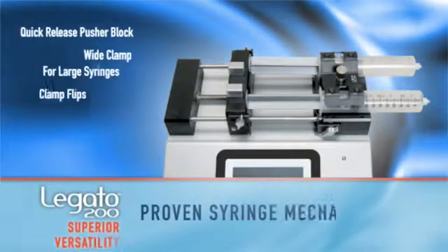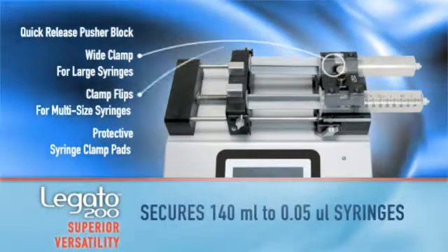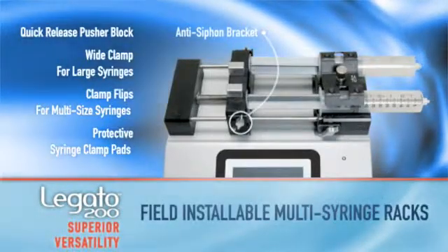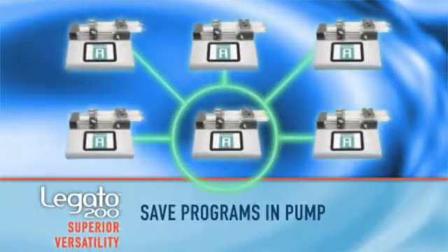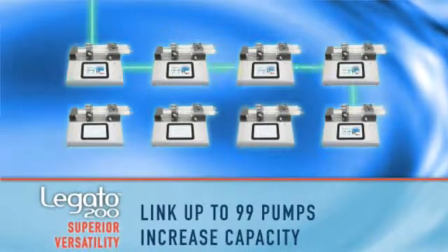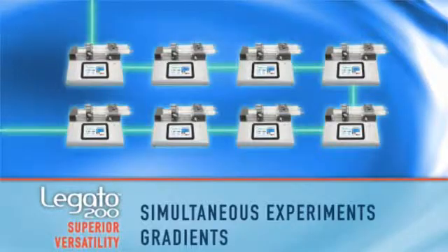Take, for example, the Legato 200's syringe mechanism. It ensures accurate flow at higher pressures with viscous fluids at 75 pounds or 34 kilograms. Recipes can be transferred from one pump to another, ensuring consistent configurations without reprogramming the pump. Multiple pumps can be interconnected for gradients, increased flow capacity, and simultaneous multi-tests.